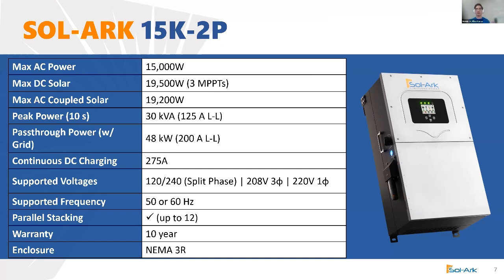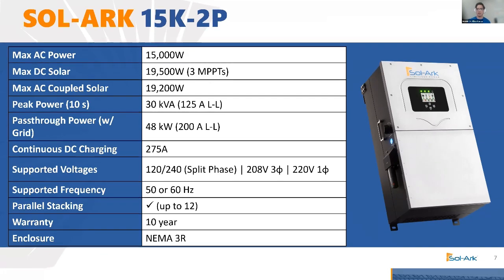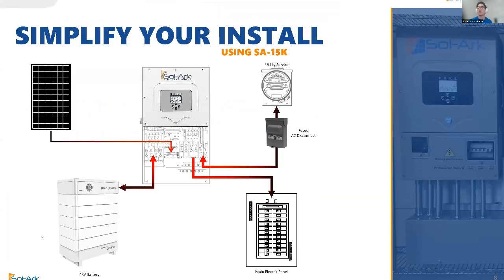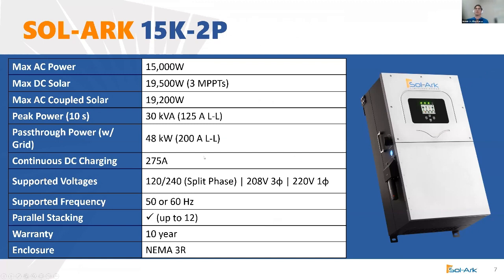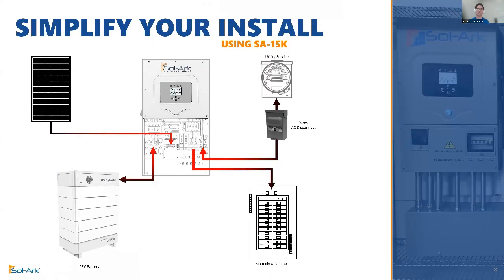Essentially you can ensure that you sell quite a bit to the grid. The grid pass-through is 48 kilowatts. You can charge and discharge at 275 amps. We support split phase, 208 volt 3-phase, and 220 single phase, depending on the wiring configuration, at 50 or 60 hertz. You can parallel up to 12 units, with a 10-year warranty and a NEMA 3R enclosure.